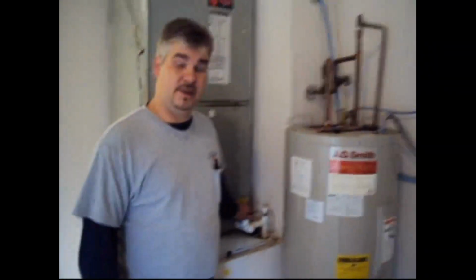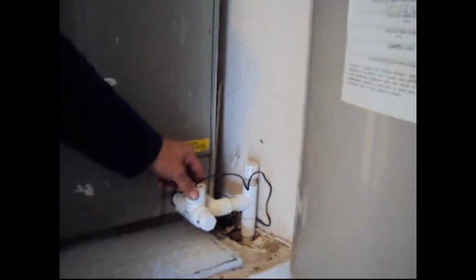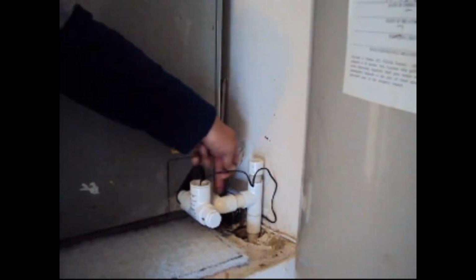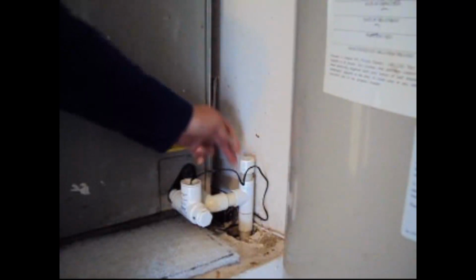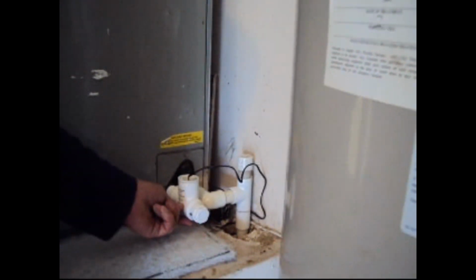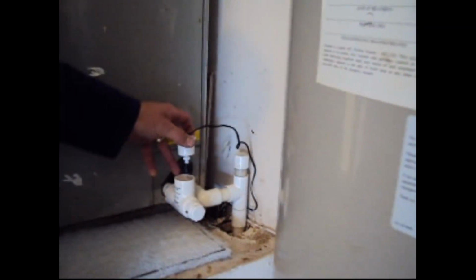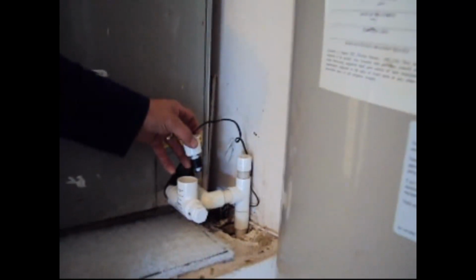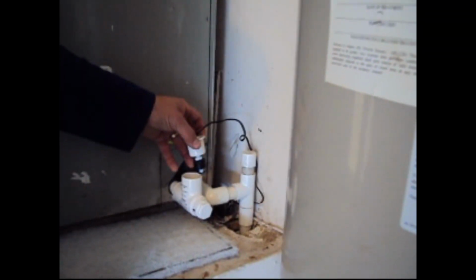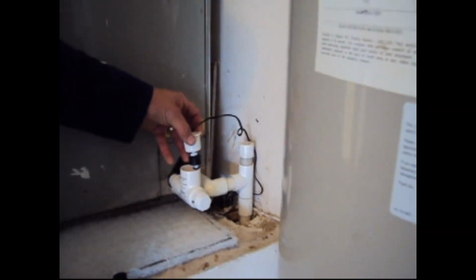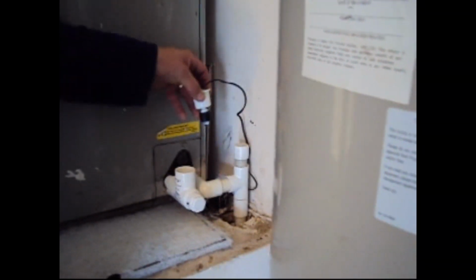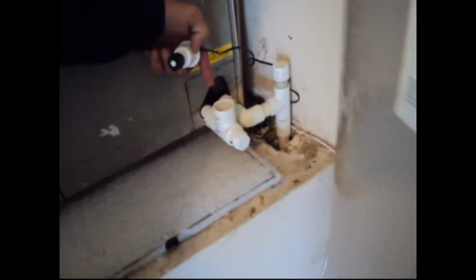Next we have a safety device. On the air handler, there's a device right here, and it's called a float switch. Its purpose is if the condensate drain, which is right here, backs up full of water, the water will come into this chamber, cause a float to rise, and shut the machine down to keep it from flooding your home or flooding your garage.